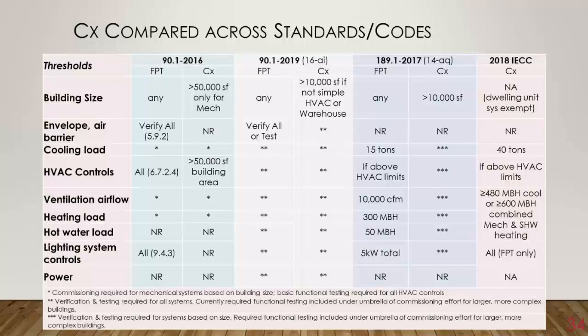Now, there did exist functional performance testing for lighting systems and controls. One interesting thing is that there was no standard document out there for a functional performance testing method for lighting controls. Now, there are plenty of suggested functional performance tests out there in the commissioning industry, and we refer to a lot of those in our informative appendix. I think we refer to about a half a dozen different sources people can get functional performance tests from.